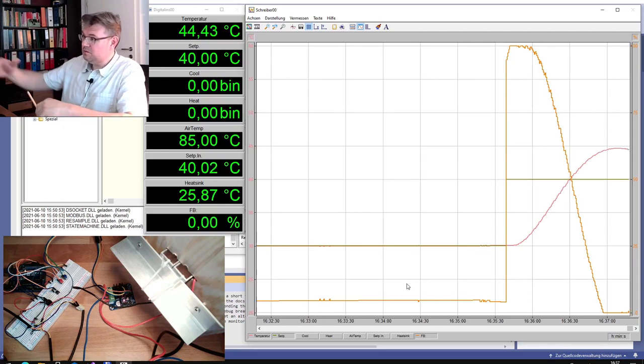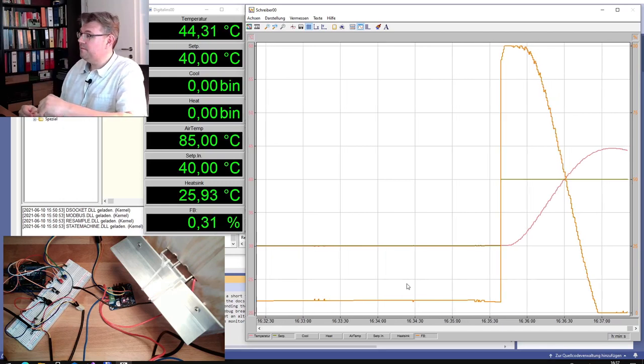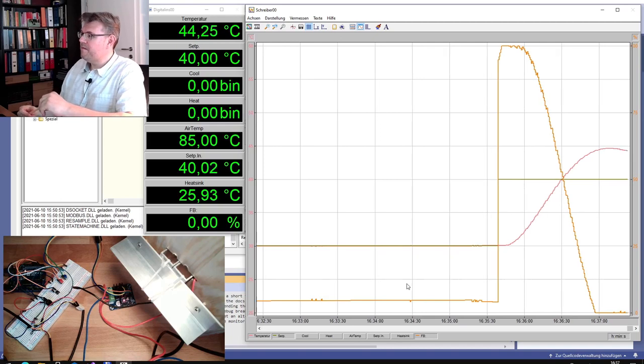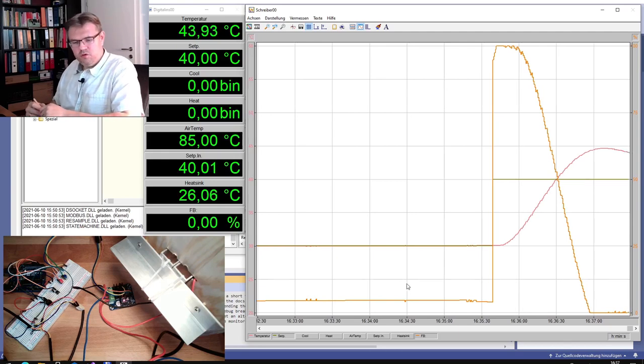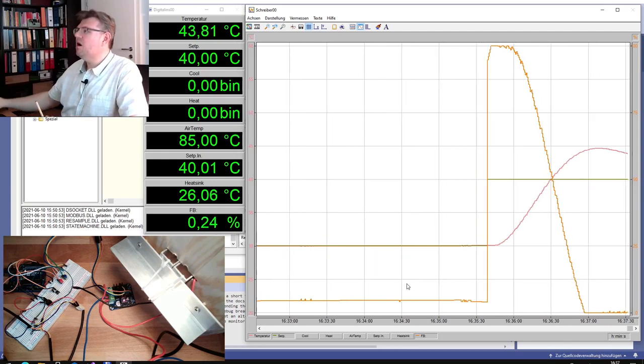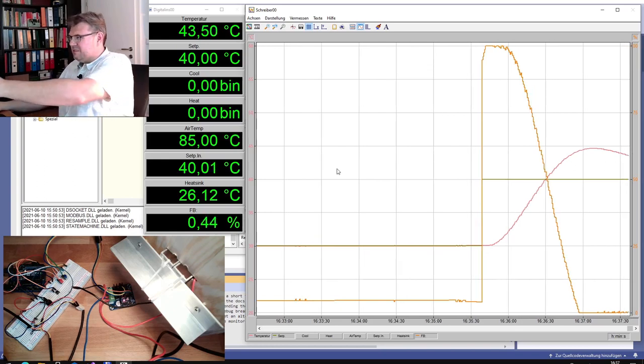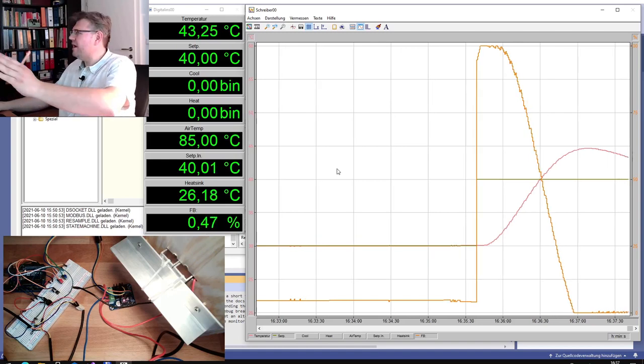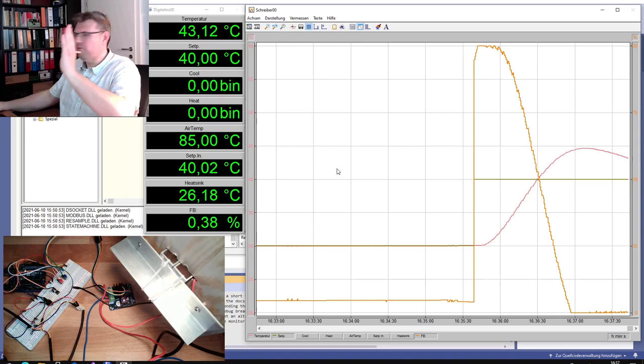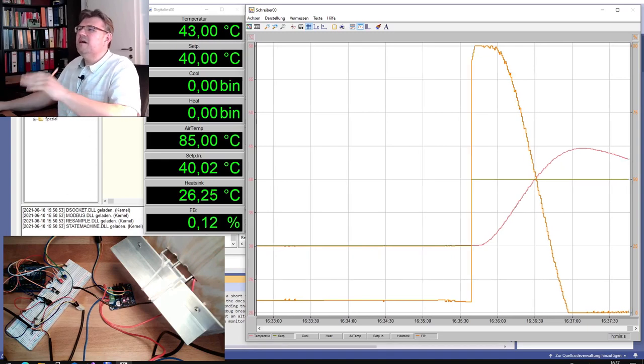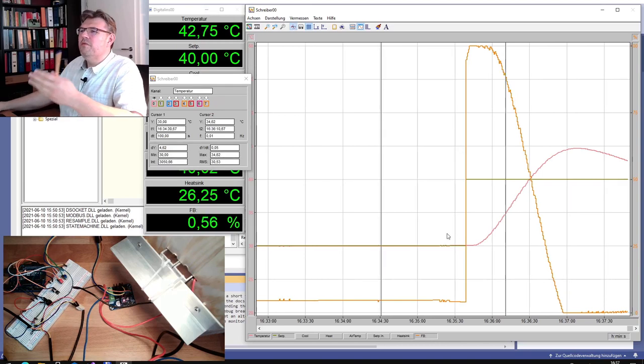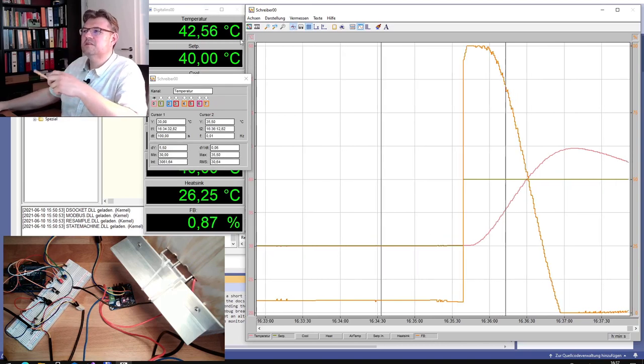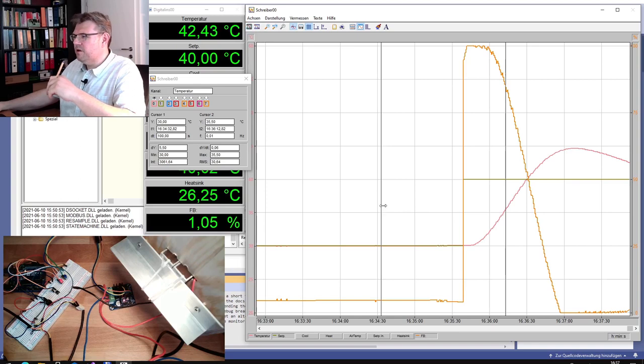So 100 percent is now 10 degrees. This is 100 percent. Now we see already a nice solid overswing. And we could tell already how big is this overswing. Therefore, and now this tool here. This is really a nice tool. It helped me through a lot of commissionings. So we can simply adjust here with two cursors. I will stop this recording.